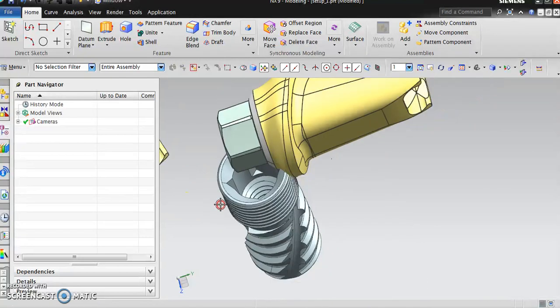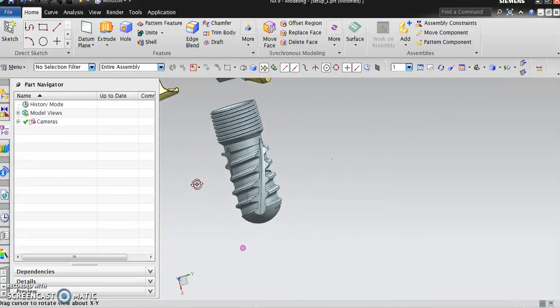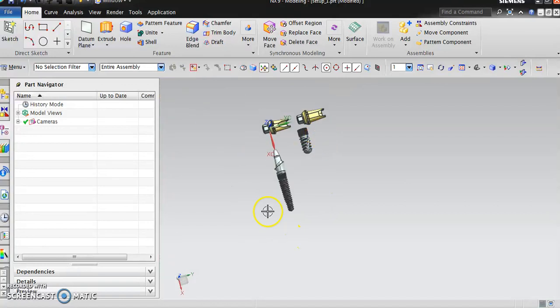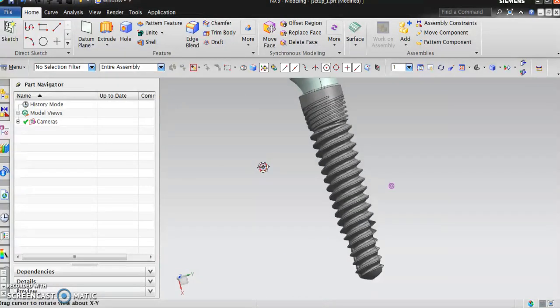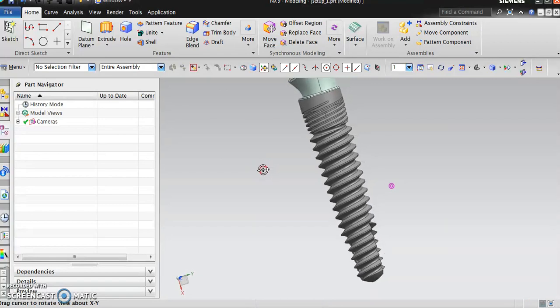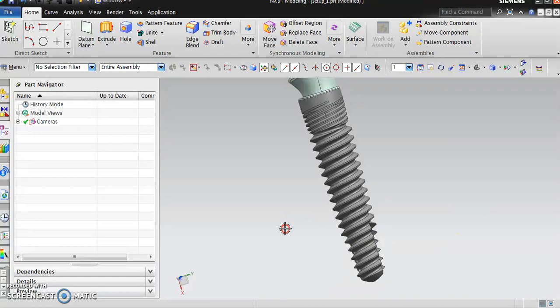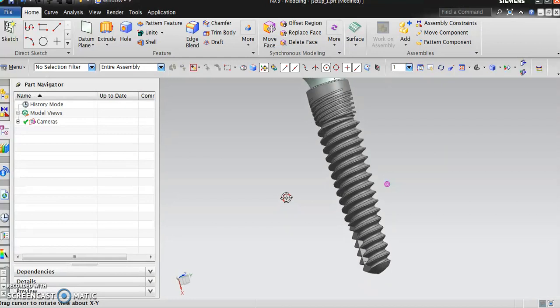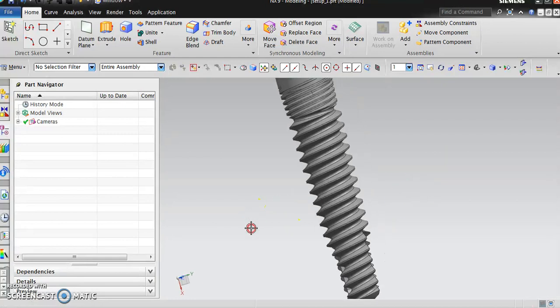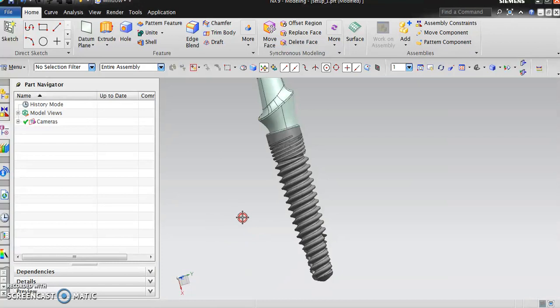The outside of the stem will be porous coated. Either we can use an anodizing solution where it will create a porous structure so the bone can grow into it, or we'll be using a common coating such as hydroxyapatite, biocompatible glass ceramics, or titanium nitride coating. Most of the systems go with the hydroxyapatite coating.